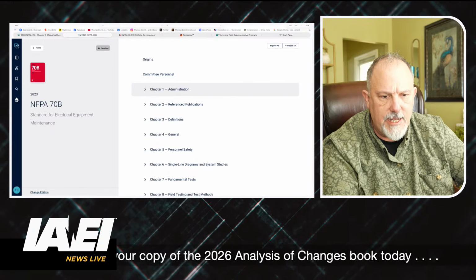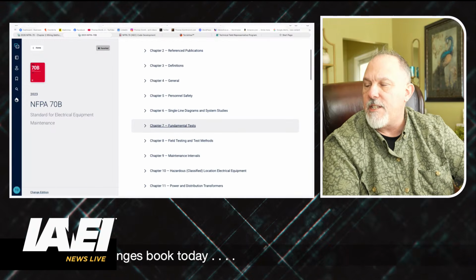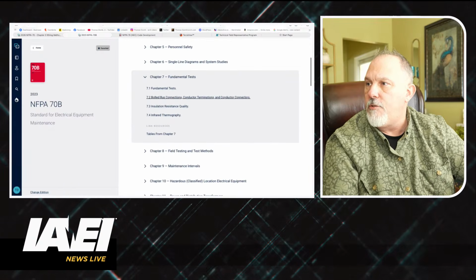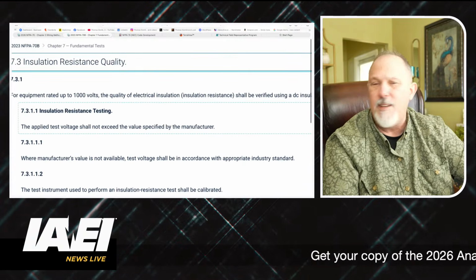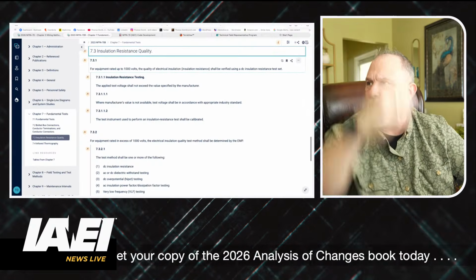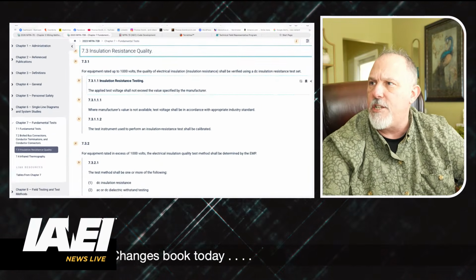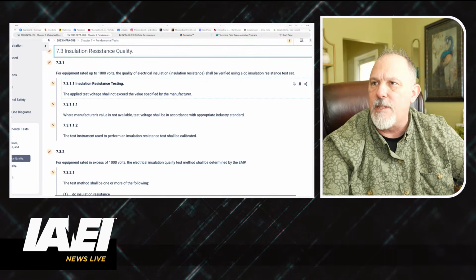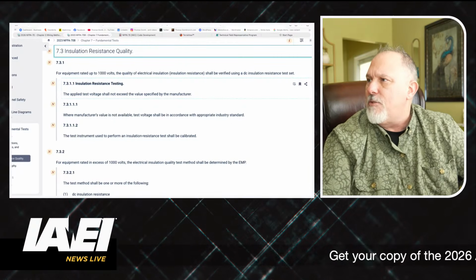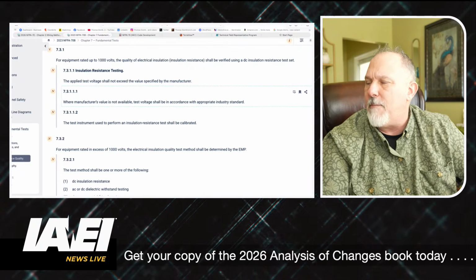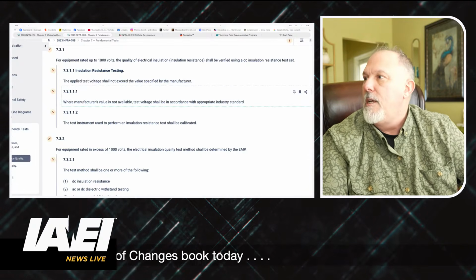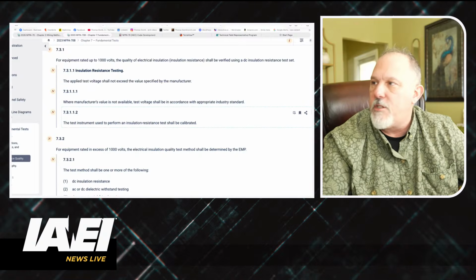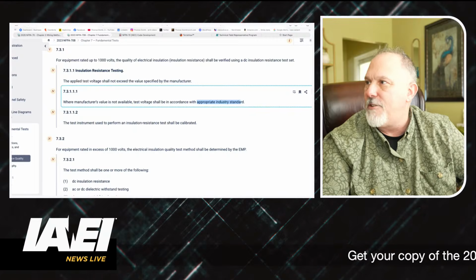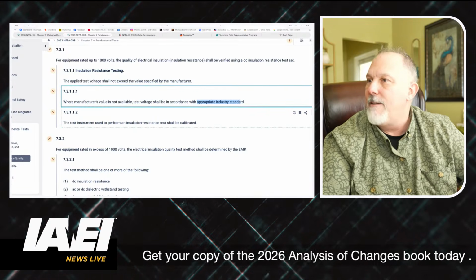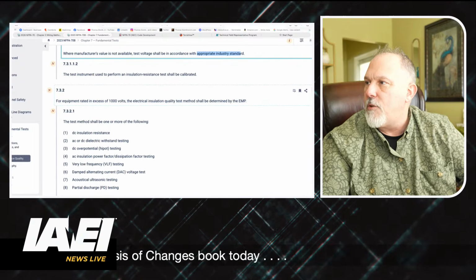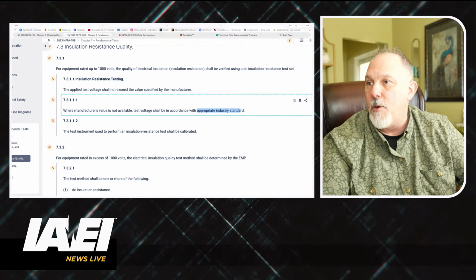Your question was insulation testing. If you go to Chapter 7, Fundamental Tests, and look at this, insulation resistance quality, boom. For equipment rated up to 1,000 volts, the quality of electrical insulation resistance shall be verified using a DC insulation resistance test set. The applied test voltage shall not exceed the value specified by the manufacturer. Call the manufacturer. Where manufacturer's values are not available, the test shall be in accordance with an appropriate industry standard. And there's no informational note. Good question. That's all it says: an appropriate industry standard.